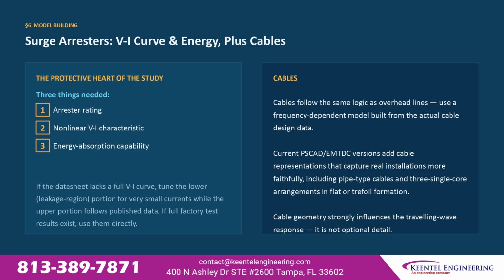3 pieces of data are required for each arrestor: the rating, the nonlinear voltage current characteristic, and the energy absorption capability. If the datasheet lacks a full VI curve, the lower leakage region portion is tuned for very small currents, while the upper portion follows published data. Full factory test results are used directly when available. Cables follow the same modeling logic as overhead lines.